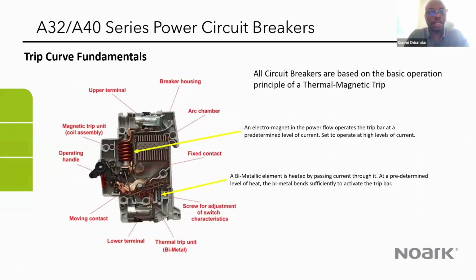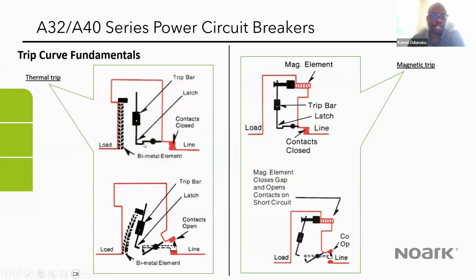So just to give you a quick run through the fundamentals of a trip unit. Like Rob said, most certainly every circuit breaker will have an electronic trip unit, but it's important to quickly talk about the thermomagnetic trip, which is something that was used in the past. Its operation uses a bimetallic element, which is just 2 metals that have different coefficients of linear expansivity, so one of the metals will expand faster than the other. When current is passing through the circuit breaker, the temperature will increase, and the bimetal strips start expanding. When it expands sufficiently, like you see in this diagram here, it's going to trigger the trip bar. And once it does that, it opens up the contact of the circuit breaker.